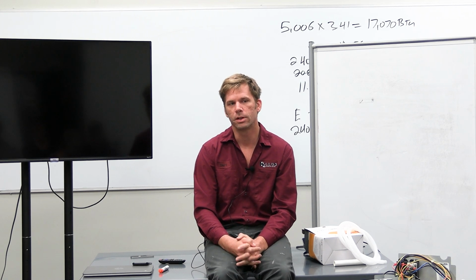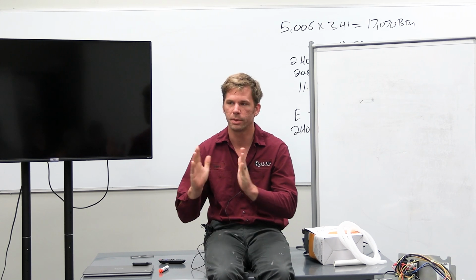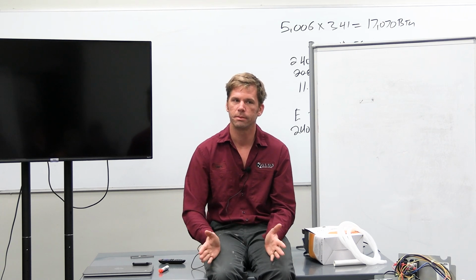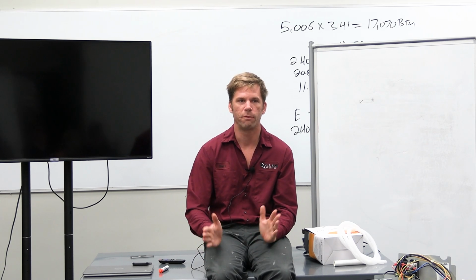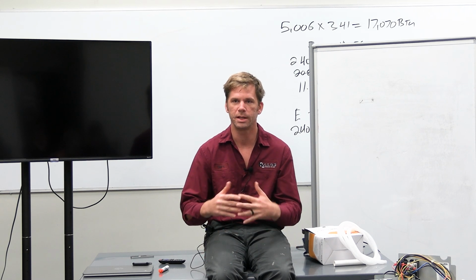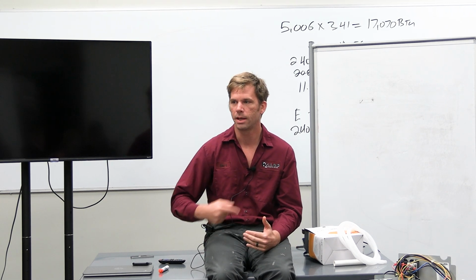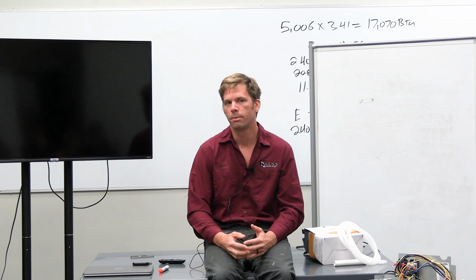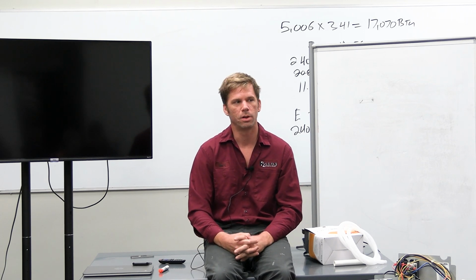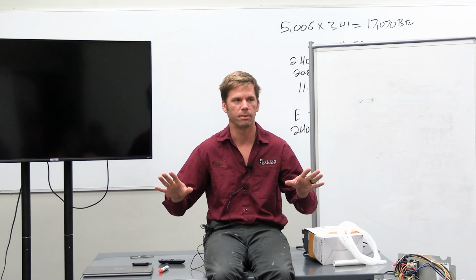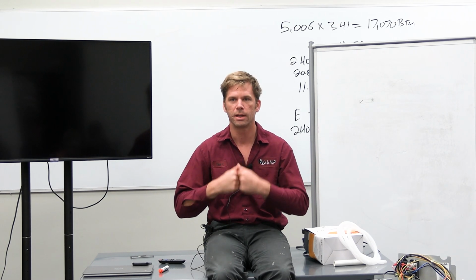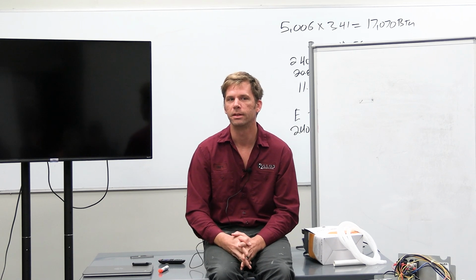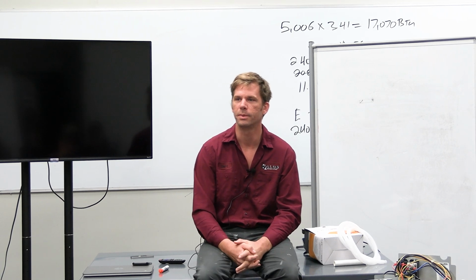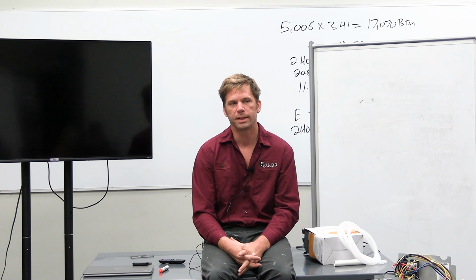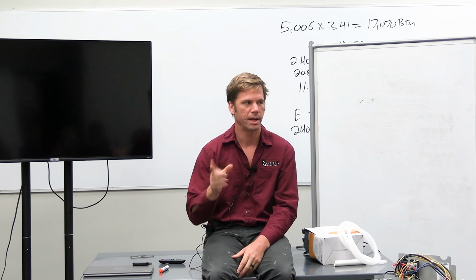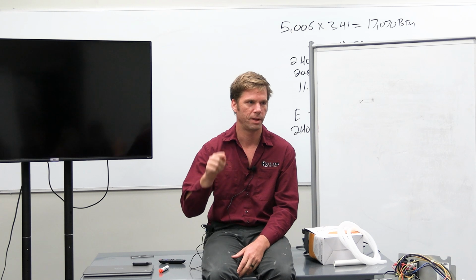So the way the flame sensor functions is that within 3 seconds of your gas valve opening, you actually need to have flame there or they're going to shut everything down and just run that inducer motor, because 3 seconds is too long to have gas flowing out into that area without a flame. You keep trying that and slowly gas is going to build up, and then the first time something does get hot enough, then we have an explosion. So you have 3 seconds for that flame to actually light and that sensor to say we have flame there.